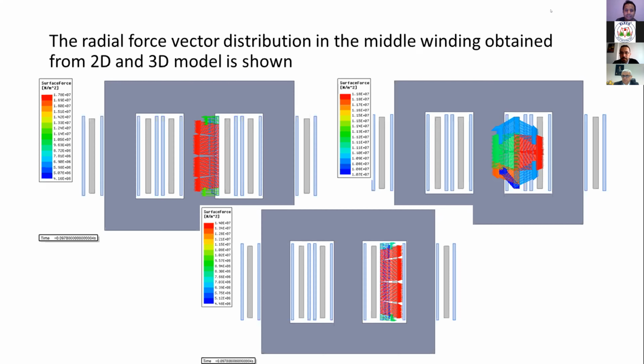You can make the distance equal, then we can conclude something. Generally the high voltage side is different, but in your work the spacing is also different between the low voltage side and the second low voltage side. Maybe that is the reason, so maybe there is another work. Yes, maybe in our study the distance is different, because we try to adjust the short circuit impedance in our transformer, so the distance is different between the two LV windings. Yes, got it.